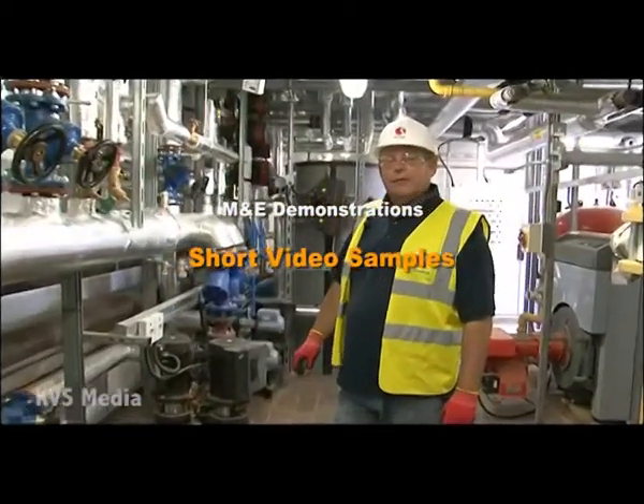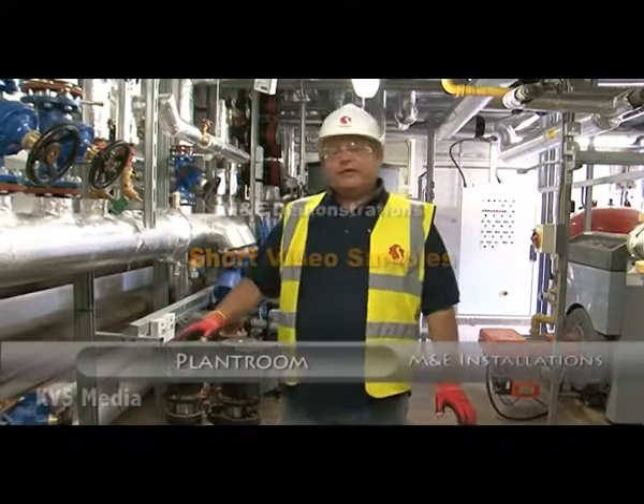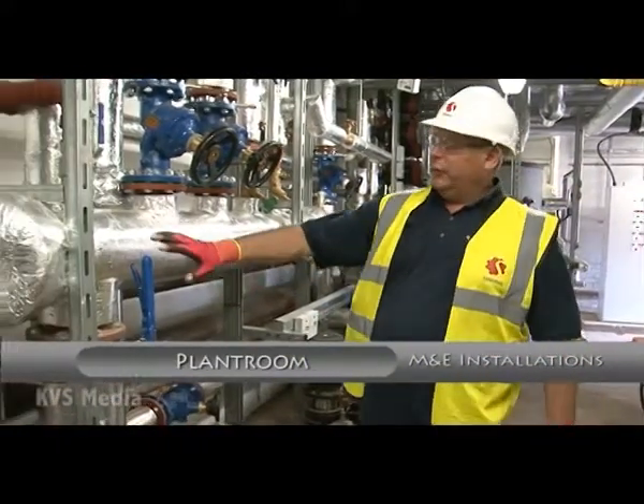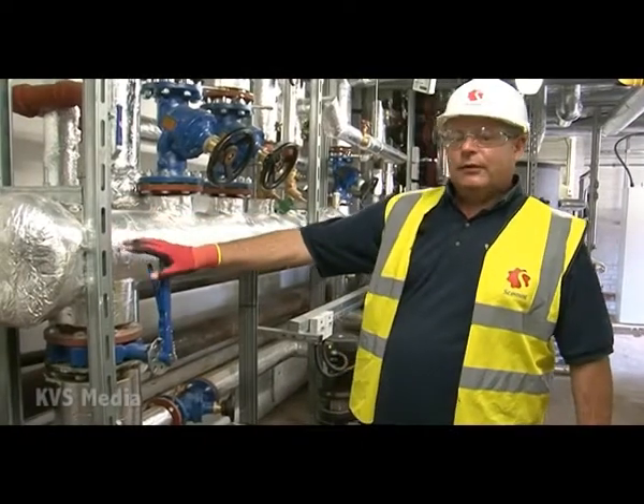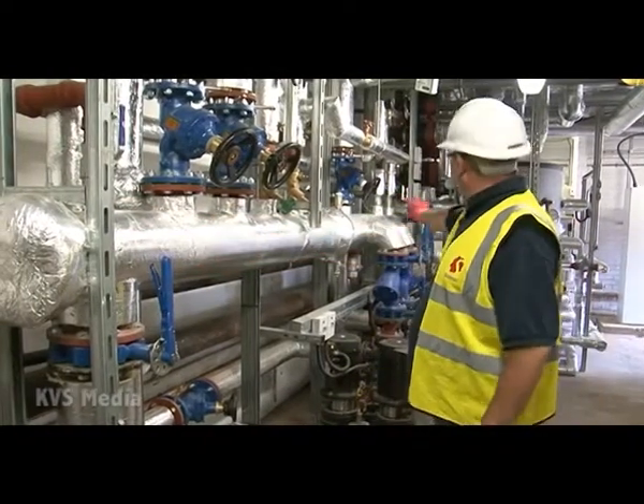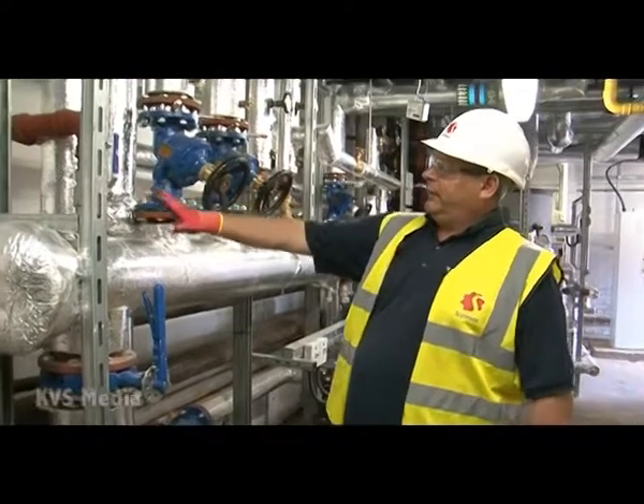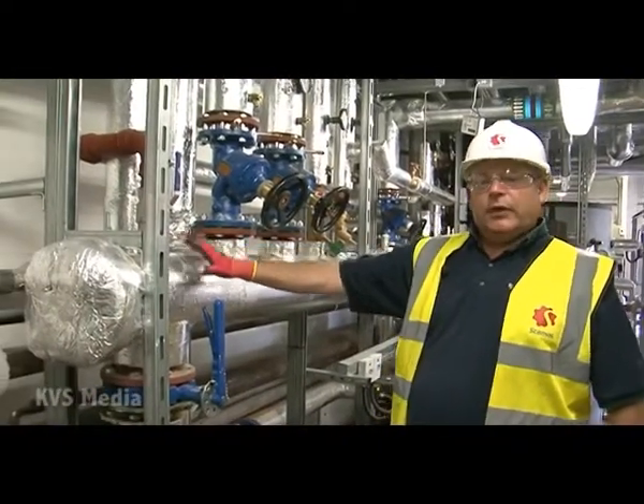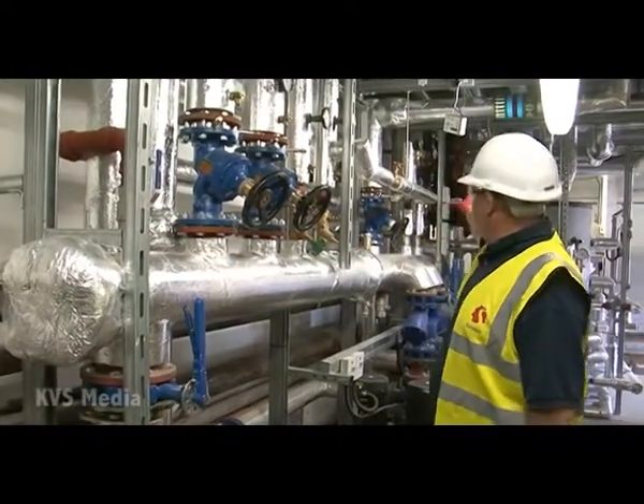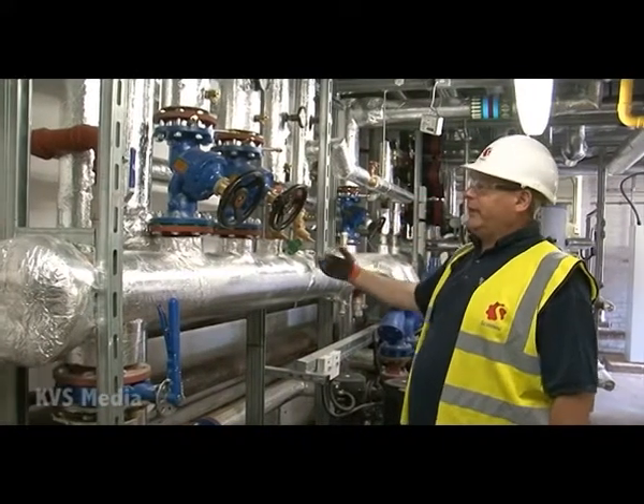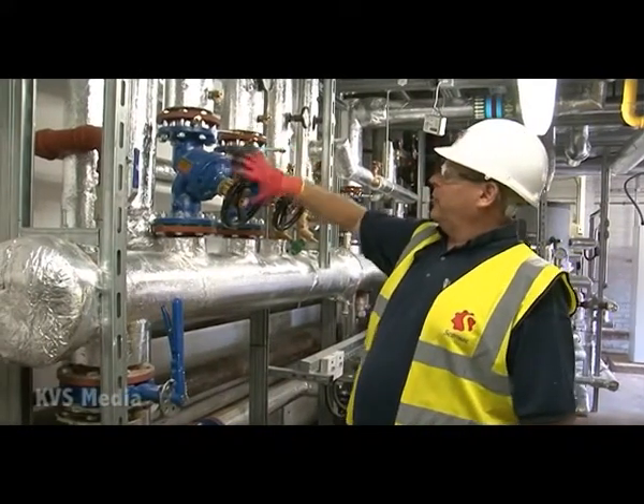We're now in the main plant room. Basically this was the existing plant room, and what we've done is we've altered the pipe work to form what's called a low loss header, which is this big long pipe here. Basically we have all the returns for the building on one end and all the flows for the building come back in on the other end and mix in the middle.